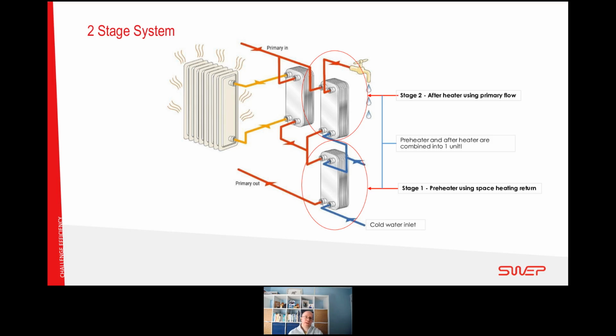It then goes into the second stage heat exchanger, which is what we call the afterheater. And then the temperature is lifted higher to the required temperature, 50, 55, 60. And that then delivers the hot water to the end user. And the key process here is that you've got two stages, two processes of transferring heat from the district heating scheme to the hot tap. And it's this combination of the preheating in stage one and the afterheating in stage two that extracts the most heat from the primary flow and the space heating return, which therefore brings the temperature lower on the primary return going back out to the energy center.